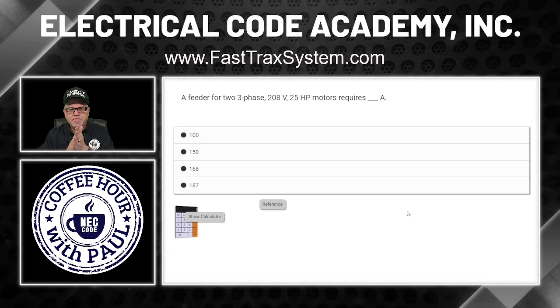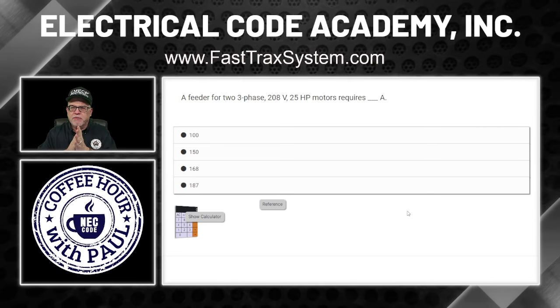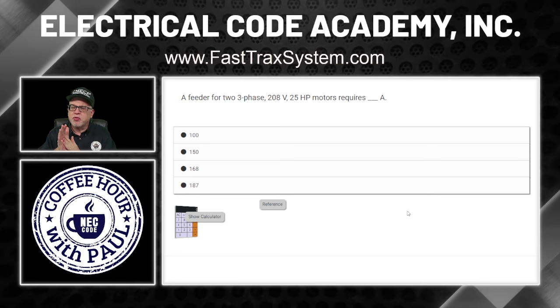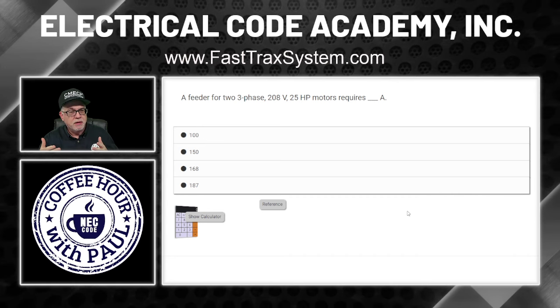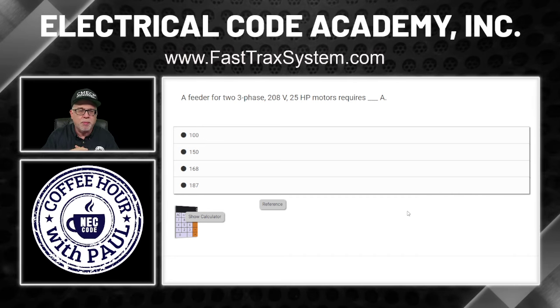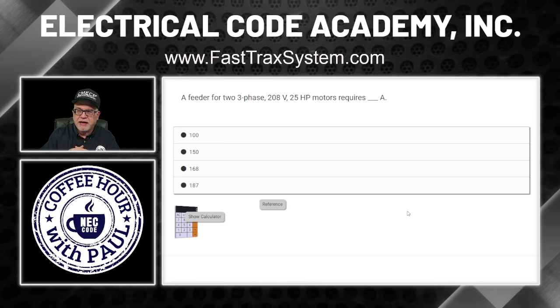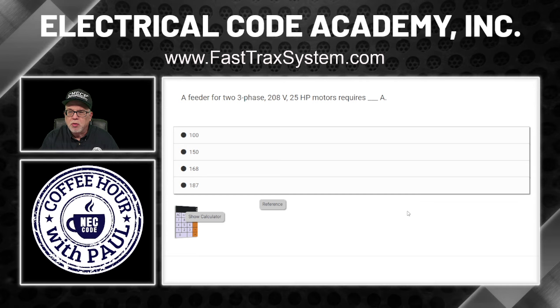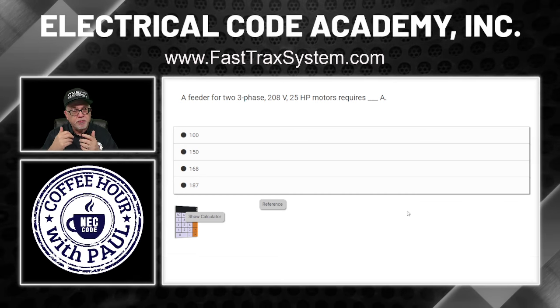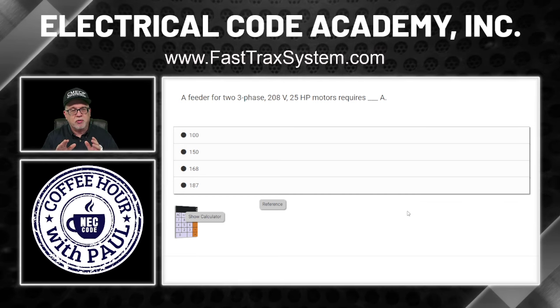Next question. Feeder for 2 3-phase, 208-volt, 25 horsepower motor requires what? Okay, this is for a feeder. Now, we obviously know we have multiple motors here, right? We've got 2 motors, not a single motor, 2 motors. So if you didn't know the answer or where to go for feeders, and where are we going for motors?